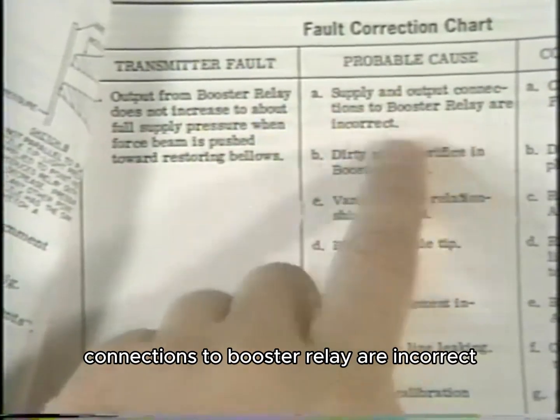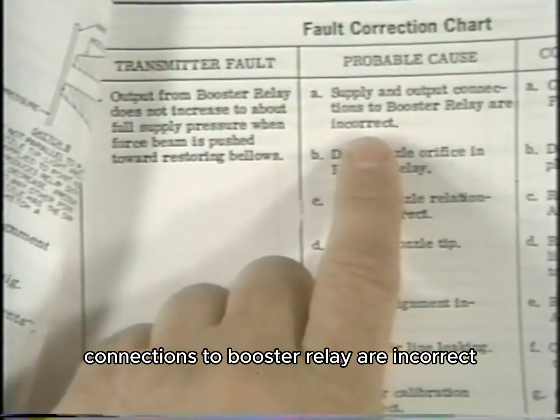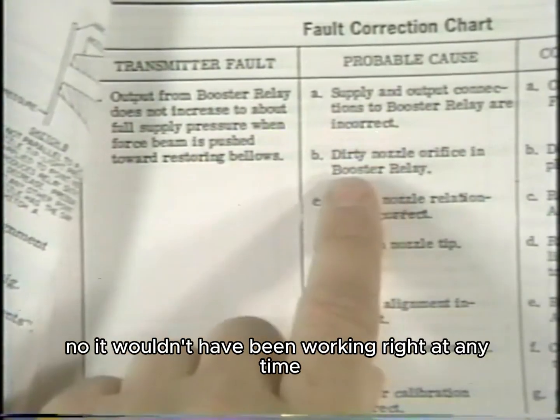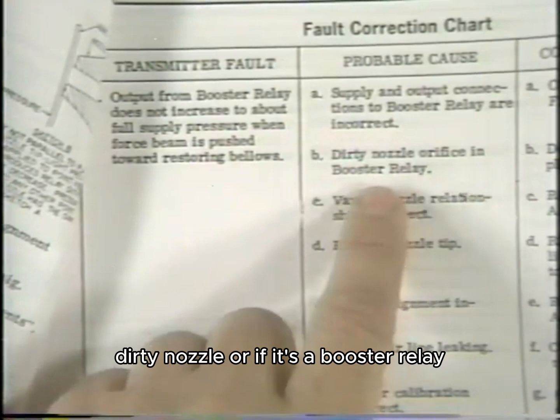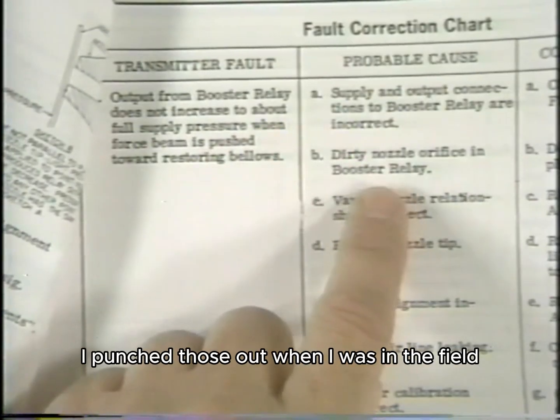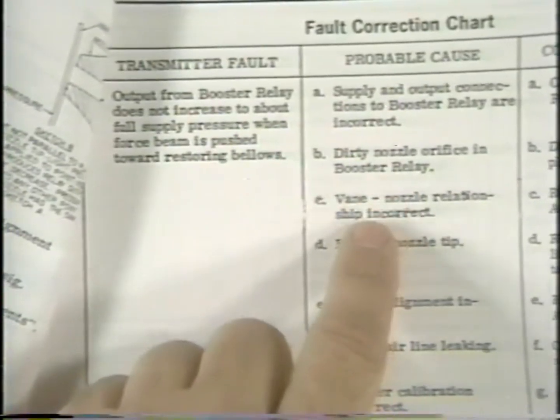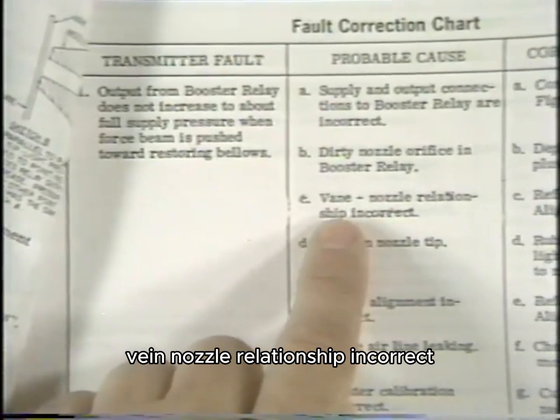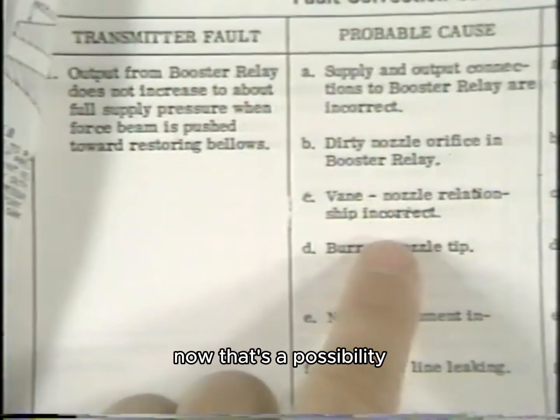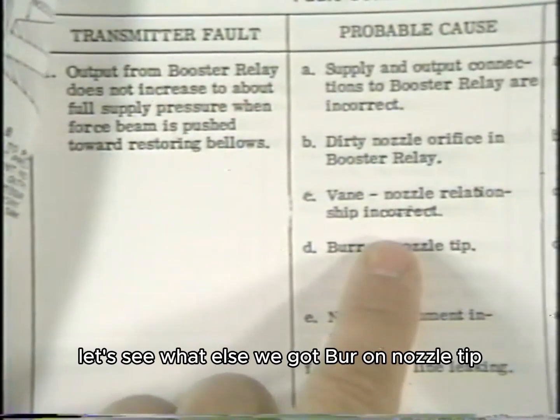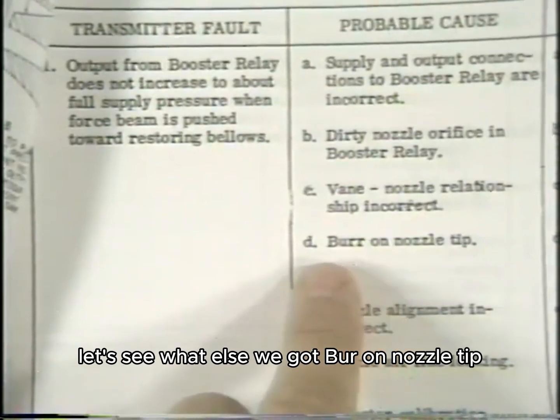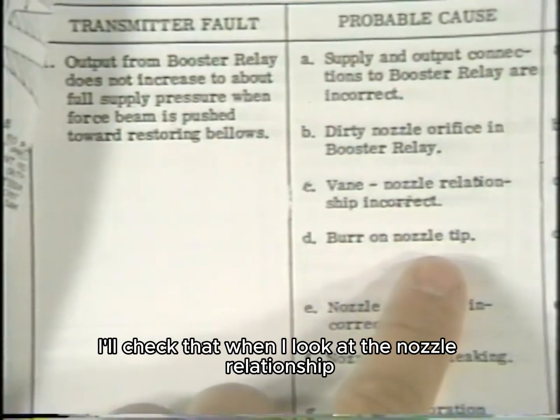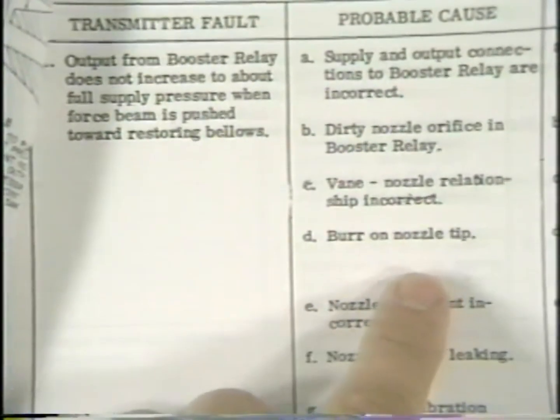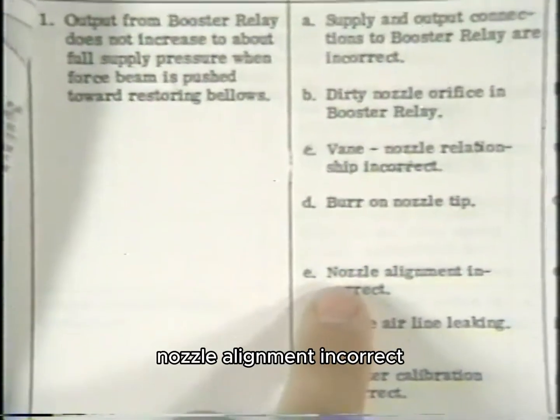Supply and output connections to booster relay are incorrect. No, it wouldn't have been working right at any time. Dirty nozzle orifice in booster relay. I punched those out when I was in the field. Vane nozzle relationship incorrect. Now that's a possibility. Let's see what else we've got. Burr on nozzle tip. I'll check that when I look at the nozzle relationship. Nozzle alignment incorrect.